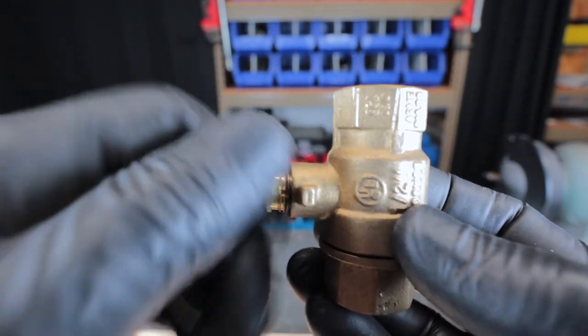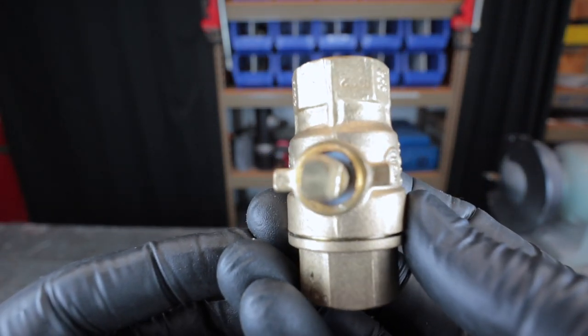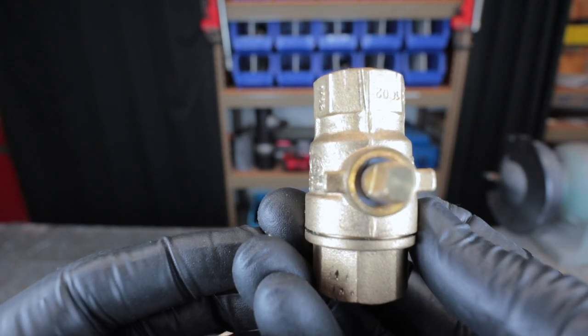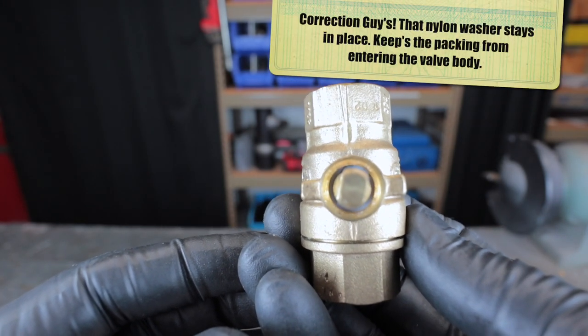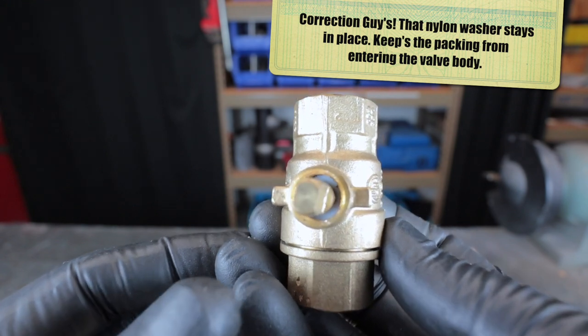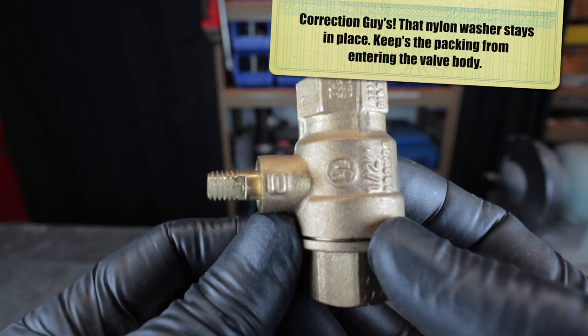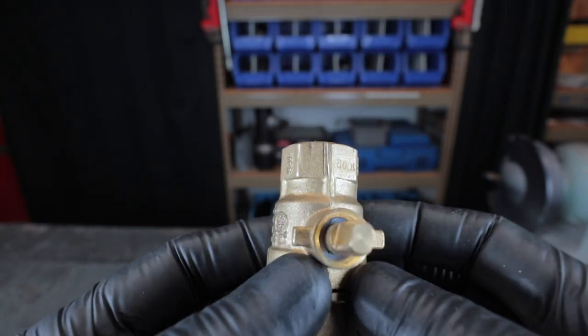I will take this little packing nut out and if you look inside there, I don't know if you can see it but there is a nylon washer in there. Generally I would remove the washer and put the packing first and then put the nylon washer back, but this is so far in that what I generally do is I just put the packing on top of the nylon washer.